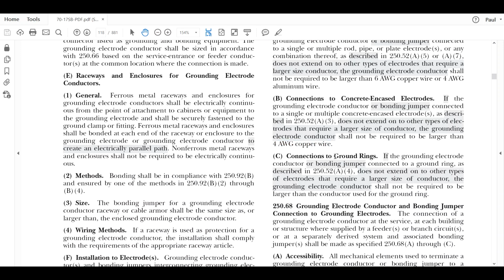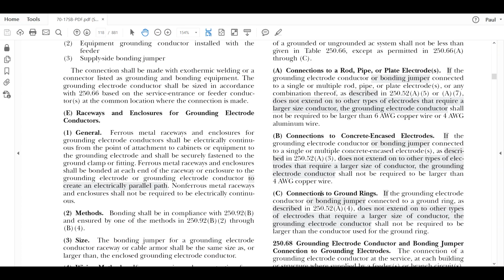And then it says here for ground rings, if the grounding electrode conductor or bonding jumper connected to the ground ring, as described in 250.52(A)(4), does not extend onto other types that are larger, then the grounding electrode conductor shall not be required to be larger than the conductor used for the ground ring, and that is a 2. Okay. If that ground ring happened to be larger for some reason, made larger than 2, maybe the engineer designed that, then it doesn't have to be larger than the conductor used. So even if you do utilize the ground ring, you've got to go with whatever the engineer specifies for it. But generally, a 2 gauge is what's required for the ground rings. Okay. All right. So that's that.